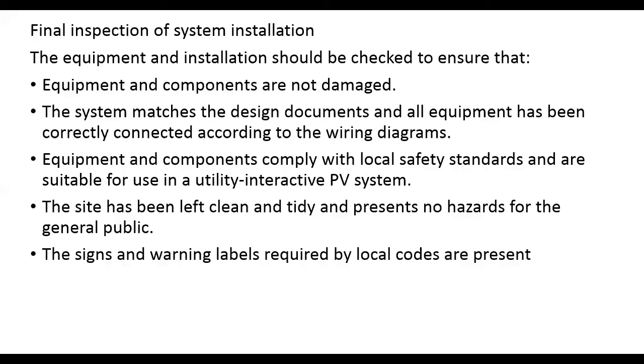It is not only that we are taking care of the inverters and other things; we have to check the wiring also, whether the wiring and the electrical components have been inspected. I cannot keep any of the wiring open, and it cannot be left loose. So I have to check my wiring, and all the inspection process has to be documented. The main thing is not only checking; all these inspection processes have to be documented, and of course a copy should be left with the customer for their records.